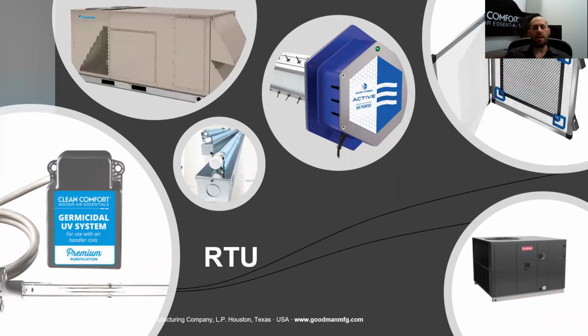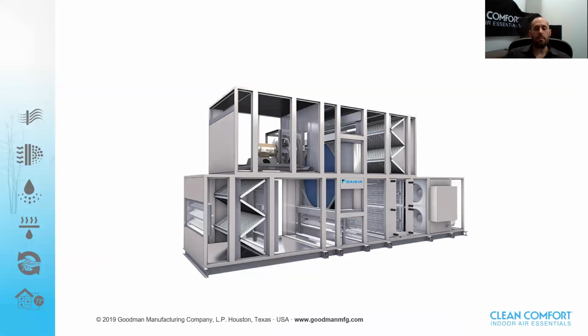Rooftop units come in a lot of sizes, so we have a lot of options. You can use UV lights either inside or outside. If needs be, you can use a purifier. You can use active or carbon, and you can use a hybrid electronic air cleaner. Custom air handler units usually have a built-in ERV wheel, and we can add filters or we can add multiple purifiers.